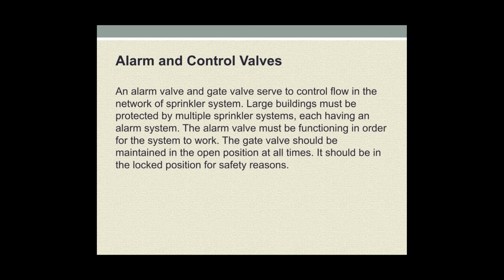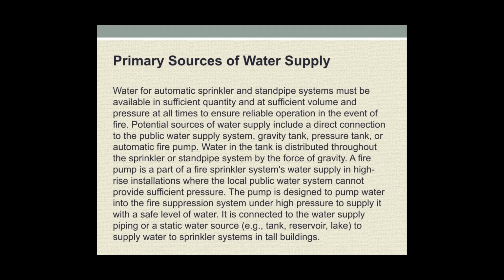Alarm and control valves. An alarm valve and gate valve serve to control the networks of sprinkler systems. Large buildings must be protected by multiple sprinkler systems, each having an alarm valve. The alarm valve must be functioning in order for the system to work. The gate valve should be maintained in the open position at all times. It should be in the locked position for safety reasons.